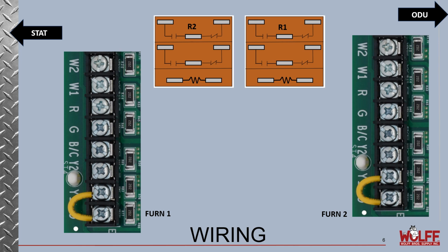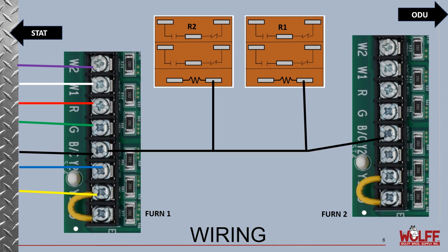So we're going to bring in our wires from our thermostat to furnace 1. Okay, next we're going to wire from common to our coils on the relay and over to the common on furnace 2. Then we're going to use W1 from furnace 1 to energize the coil on relay 1. And W2 from furnace 1 to energize the coil on relay 2.